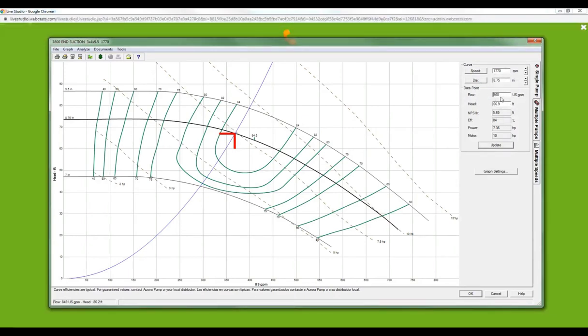Okay, this application is looking for 368 gallons per minute at about 67, almost 70 feet of head. Suppose that we needed to reduce this flow rate from 368 down to 200 gallons per minute. We could do that by closing a valve. If we did that, I need to take this 368 and get it down to 200. Say update, and that goes up to 73.4 feet of head at 200 gallons per minute. So we will have moved up the pump curve to 200 gallons per minute, right about there. We've increased the head, we've decreased the flow.